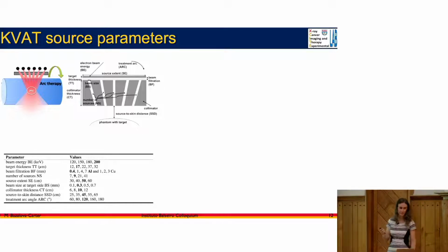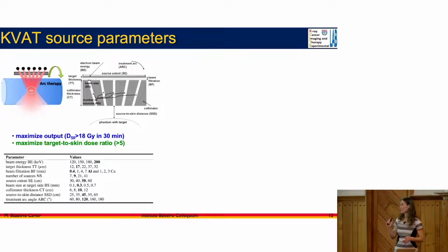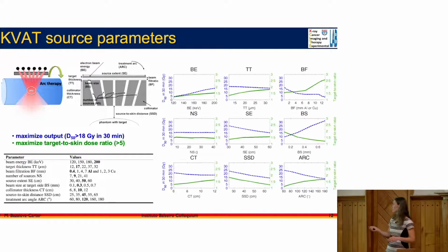And the goal for us to make this clinically feasible was to maximize the output. So we wanted to be able to deliver 18 gray to the patient in 30 minutes. Of course, if you put a lot of filtration in the beam, you'll get higher energy beams, but the output will decrease. And we cannot have patients on the table for 20 hours, right? That's just not feasible. So the requirement of Michael was to deliver 18 gray in 30 minutes. And he also wanted to achieve a target to skin dose ratio higher than 5. So 20% on the skin, 100% in the target. So this was our goal. For this parameter study that we ran, it was lots of simulations that I'm showing very briefly over here.